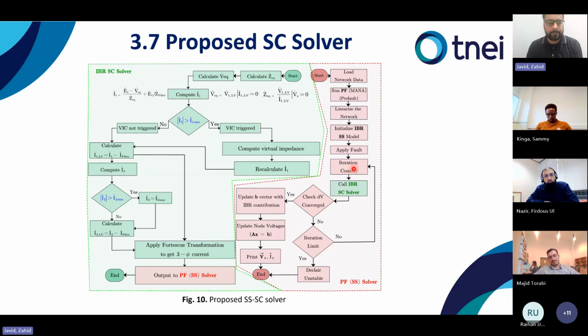After applying a fault, we start an iteration counter, which calls this solver on the left hand side, shown in green. It calculates Z equivalent and V equivalent with these equations, and computes I1, the positive sequence current. Then it checks if the positive sequence current is greater than Imax; if so, it triggers the virtual impedance, computes the virtual impedance accordingly, and recalculates I1. If the current is less than Imax, the virtual impedance is not triggered, and then we can calculate the current on the LV side of the transformer.